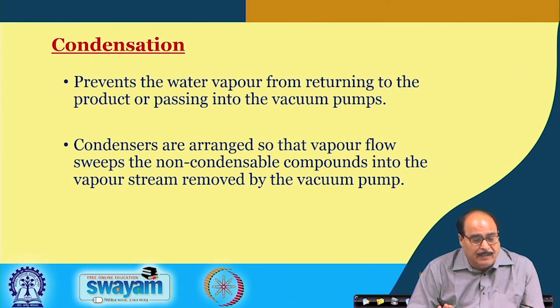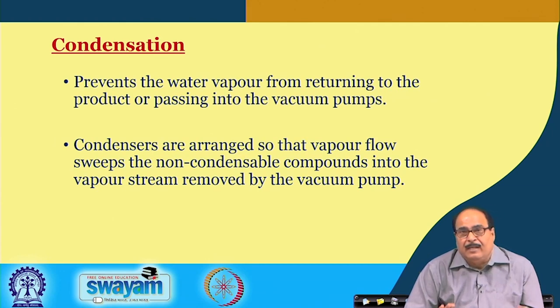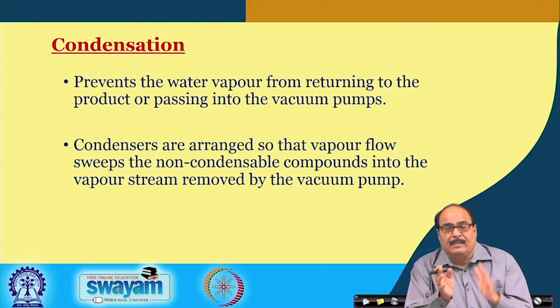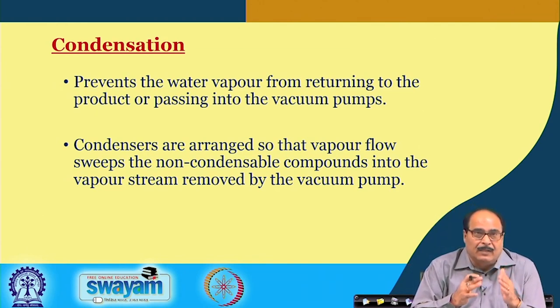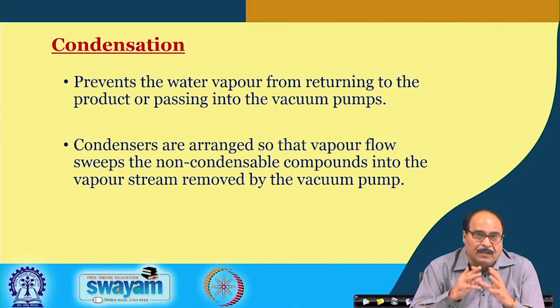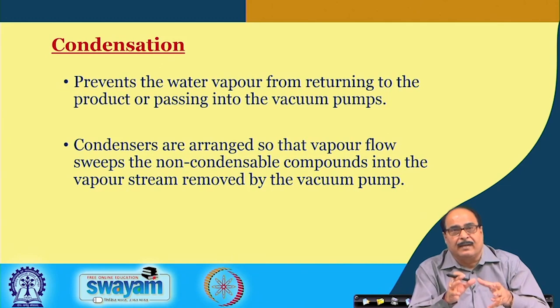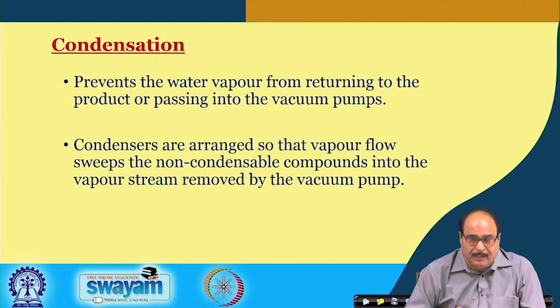Condensation prevents the water vapor from returning to the product or passing into the vacuum pump. Condensers are arranged so that the vapor flow sweeps non-condensable compounds into the vapor stream, which are then removed by the vacuum pump. Effective condensation is very important because the rate of sublimation and mass transfer is greatly influenced by proper condensation. The moisture sublimed in the gas phase is condensed and converted into ice, then removed from the system.